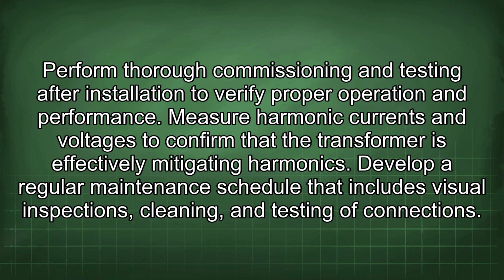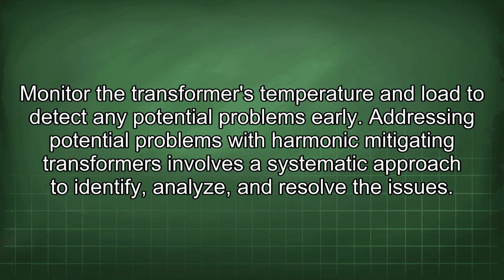Perform thorough commissioning and testing after installation to verify proper operation and performance. Measure harmonic currents and voltages to confirm that the transformer is effectively mitigating harmonics. Develop a regular maintenance schedule that includes visual inspections, cleaning, and testing of connections. Monitor the transformer's temperature and load to detect any potential problems early.